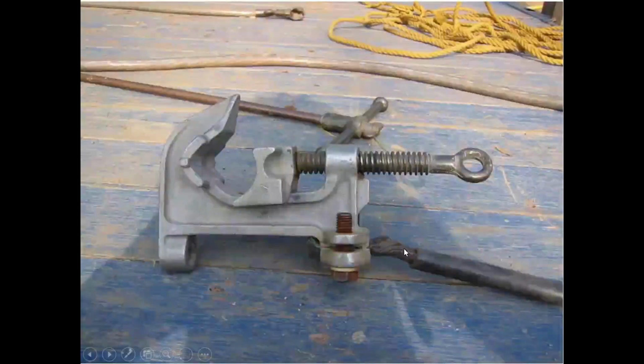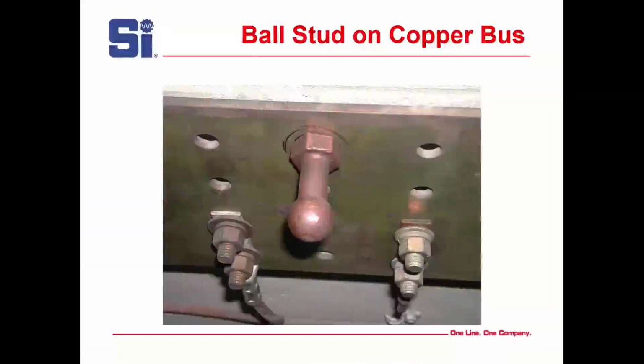You can see that it's got corrosion. The connection itself is not good. There's a lot of things going on that's not good with it. Here's my favorite, a ball stud. ASTM F855 has done testing and has found that ball studs give you the lowest impedance of any type of ground you can use. Now, if that doesn't wake you up and make you write a note, I don't know what does. But these are the best things you can use for grounding.